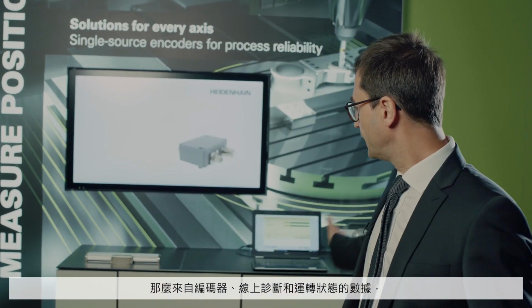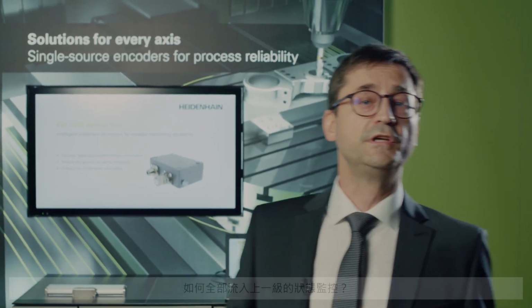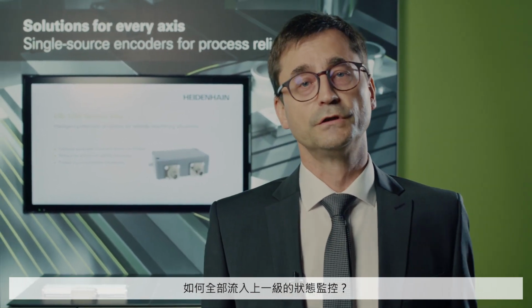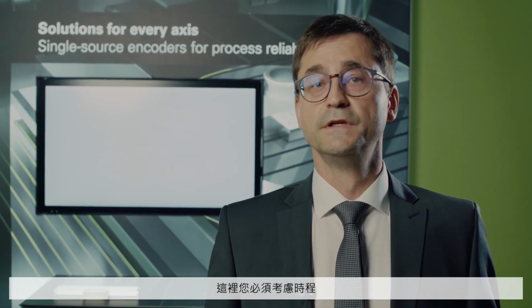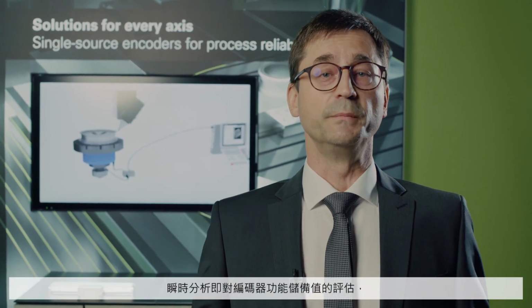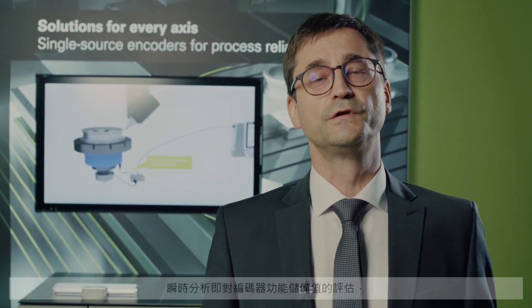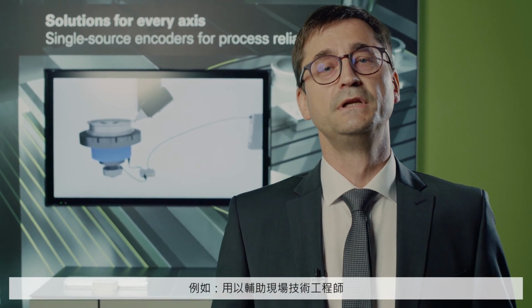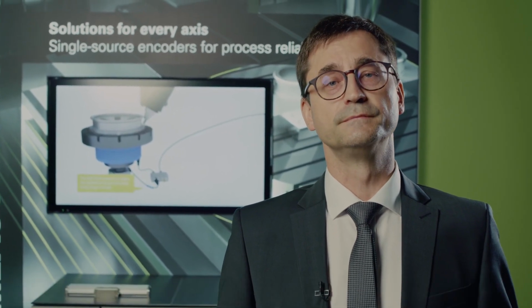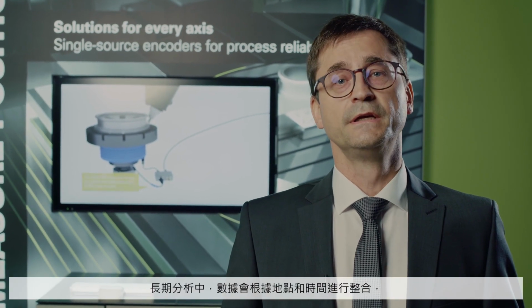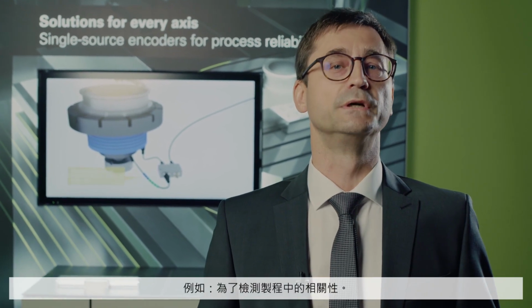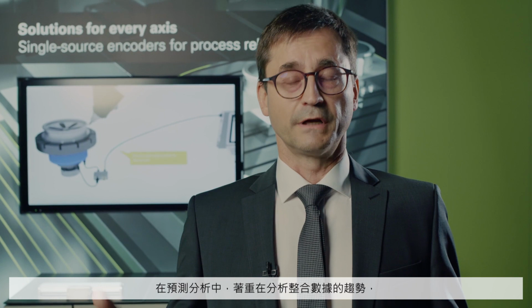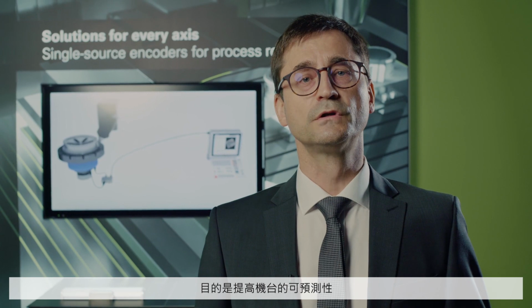So how do data from the encoder, from the online diagnostics, and from the operating status data all flow into higher-level condition monitoring? You have to consider the time horizon here. The momentary analysis deals with the evaluation of encoder function reserves, for example, in order to assist a service technician on site. In a long-term analysis, the data are consolidated with regard to place and time, for example, in order to detect dependencies in processes. In a predictive analysis, the focus is on analyzing the trend of the consolidated data, with the intention of increasing the planning capability for machines.